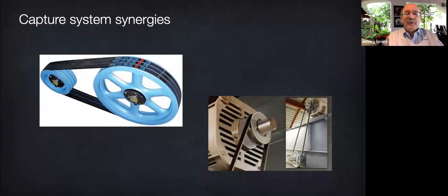But then you have to use a soft start device or a stretchy flat belt like the Swiss Habasit, because otherwise the inertia of starting up a big centrifugal fan is going to tear the teeth off the cogged belt. Fortunately, most good inverters have a soft start feature. Moreover, if you didn't carefully select your premium efficiency motor, it may run faster than the old inefficient one. That could waste more energy on excess speed and flow than it saves through greater efficiency. So you're going to have to readjust speed by changing the ASD frequency or sprocket size, or in a pump, trimming the impeller. The first of those options is the simplest. You just turn a knob to change the motor speed. So it's simplest, cheapest, easily reversible.